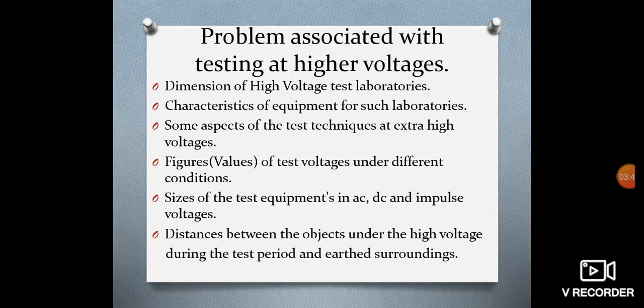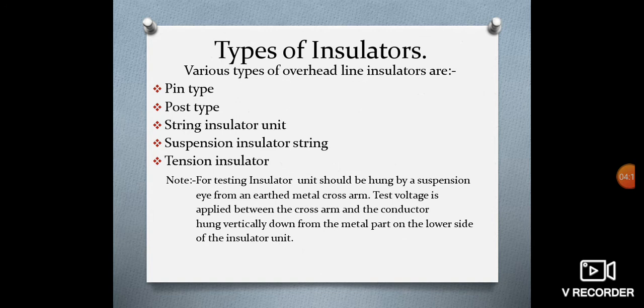Sizes of the test equipments in AC, DC and impulse voltages. Even the size of the equipment is different, and the equipments are different for AC, DC and impulse voltage testings. Distances between the objects under high voltage during the test period and earth conditions. The distance between the objects under high voltage and the earth surroundings is to be maintained, and it should be properly taken into consideration. So one by one we'll understand the high voltage testing of power system equipments.